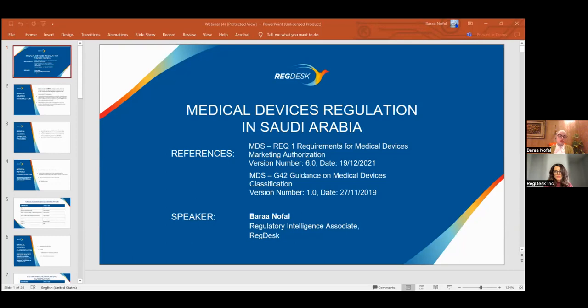But this was the same as the EU or GHTF main countries classification. So Saudi Arabia will not accept any classification that is not listed in this table. As we all know, the classification is risk dependent. As you see in the slide, class A is low risk, and there are types within class A, but it will still be class A because it is supplied sterile, or is a reusable surgical instrument, or incorporates a measuring function. Even if it is low to medium risk, Saudi FDA will classify this device as class A.